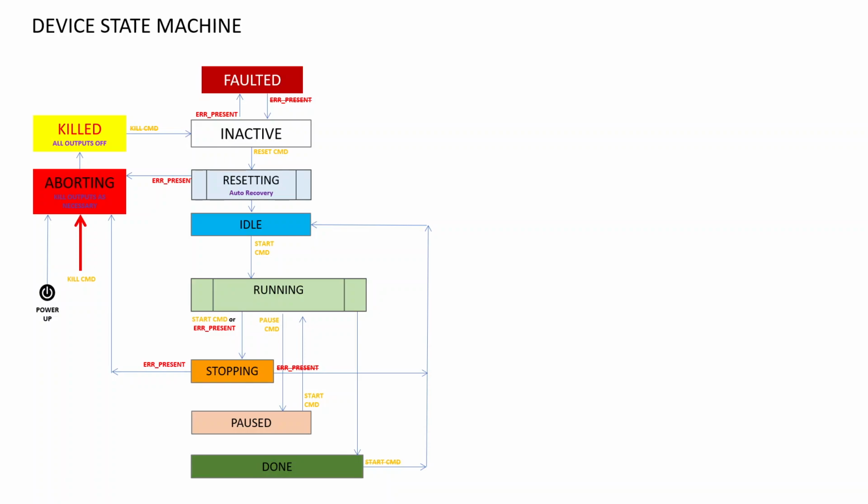So if a device happened to contain something like a motor drive, you'd want to disable that drive in this state. So we do this at power up. We also do this whenever we issue a kill command to the device. Typically, a kill command is going to come whenever an e-stop is triggered. Most of our devices are dependent upon the e-stop circuit as their energy provider.